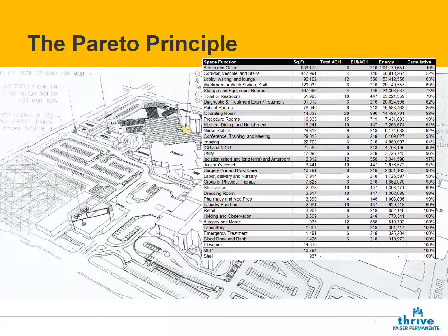The 80-20 rule says that where we should be focusing most of our effort, in order to get to 80% of the energy intensity at this facility, we're talking admin, office, corridor, vestibule, stairs, lobbies, workrooms, staff rooms, storage and equipment rooms, toilet rooms, restrooms, and then diagnostic and treatment, and you're done with the 80-20 rule. Patient rooms don't even make it into the 80-20 rule on a hospital.